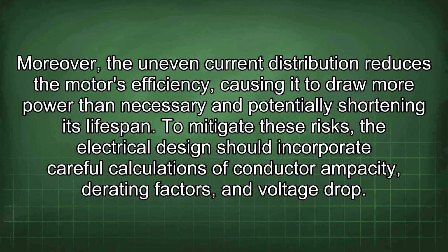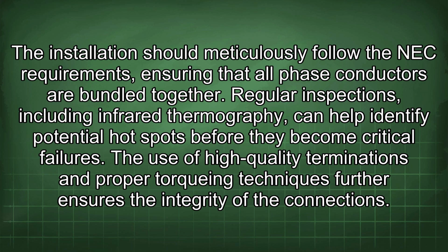To mitigate these risks, the electrical design should incorporate careful calculations of conductor ampacity, derating factors, and voltage drop. The installation should meticulously follow the NEC requirements, ensuring that all phase conductors are bundled together. Regular inspections, including infrared thermography, can help identify potential hotspots before they become critical failures. The use of high-quality terminations and proper torquing techniques further ensures the integrity of the connections.